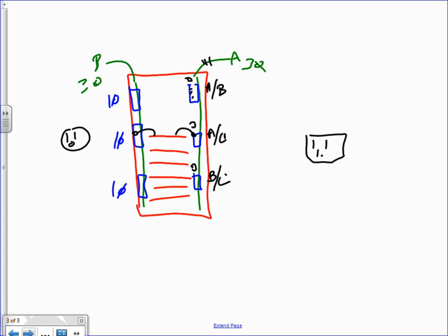So we have to educate the folks who install these servers and plug them in to either spread it out across the different phases and the phase relationship, or get a longer cord and plug this one up here, which then as they fill it up, you've got to plug that one down here. So there's a plug management issue in these data centers we have to pay close attention to. Otherwise, if we have an imbalance, we're stranding power, because we can't add more to B and C even though there's lots of capacity on phase A, since as a system we're going to start tripping breakers.